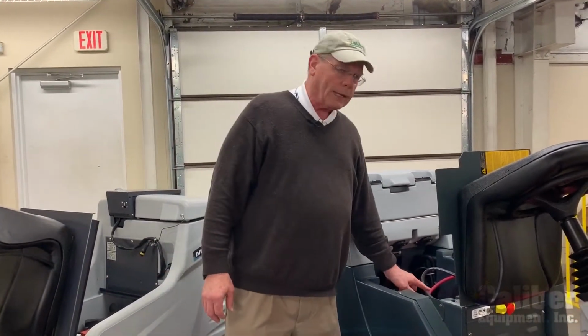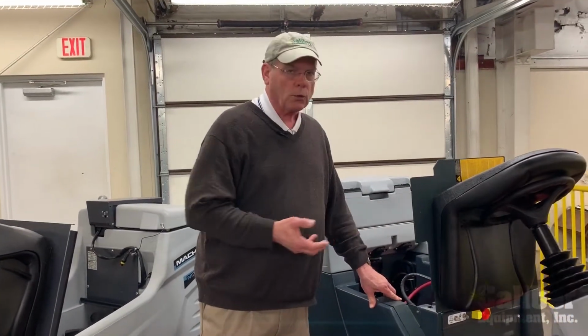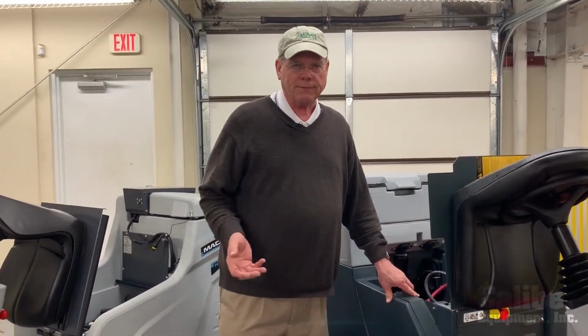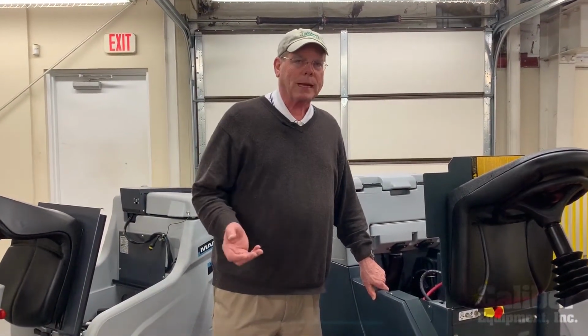So lead acid has the ability to lose the water as vapor, and when it comes out of the battery, it's also a very acidic solution, and it can actually corrode certain things in its environment. It's one of the reasons why we like plastic tanks, because plastic is impervious to any of the acidic fumes that might be coming out of the battery.